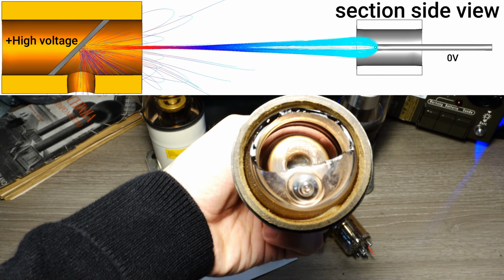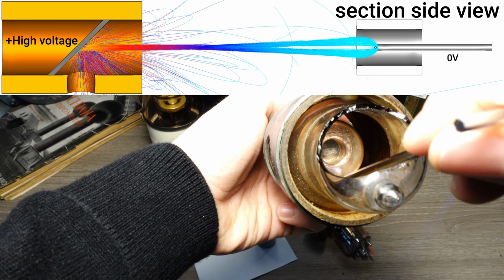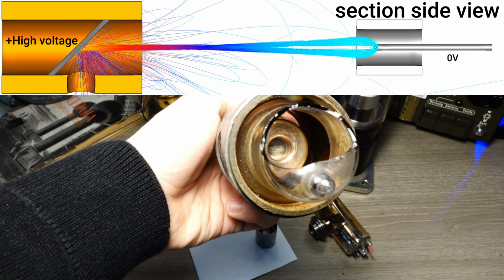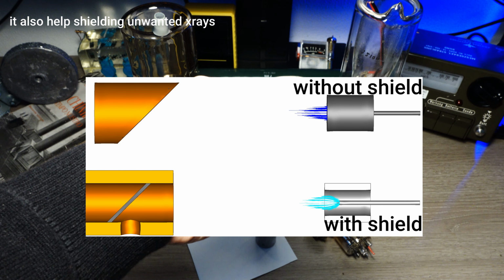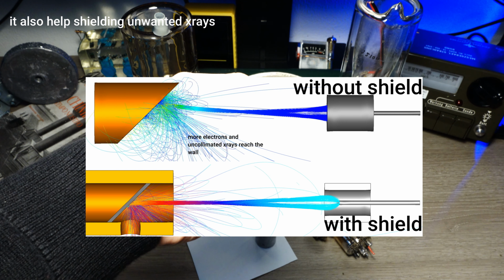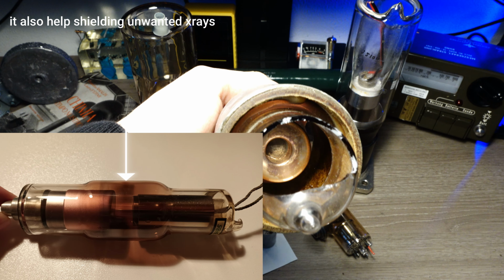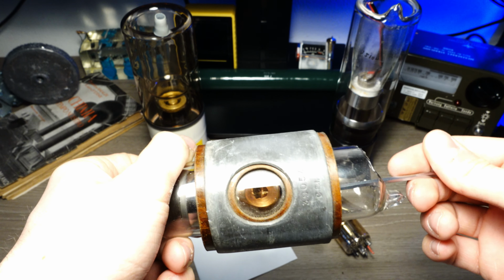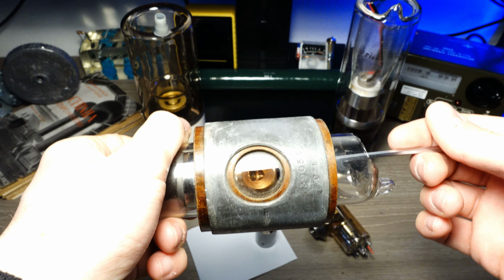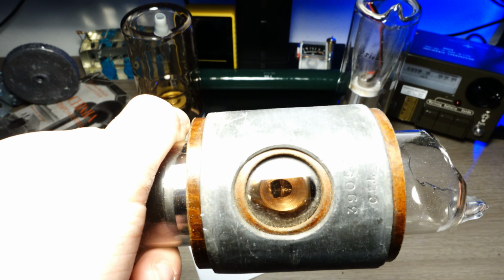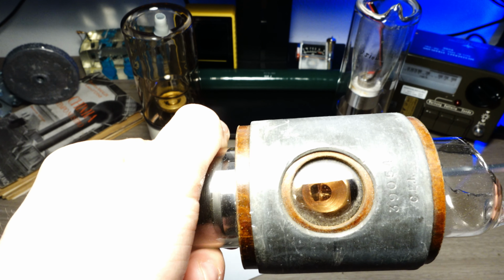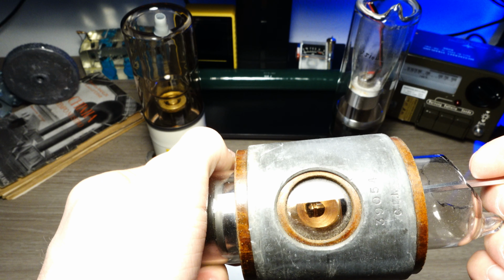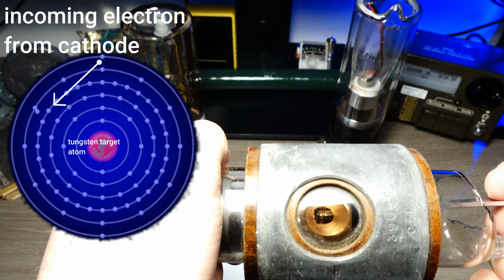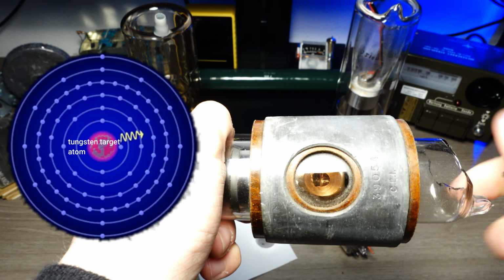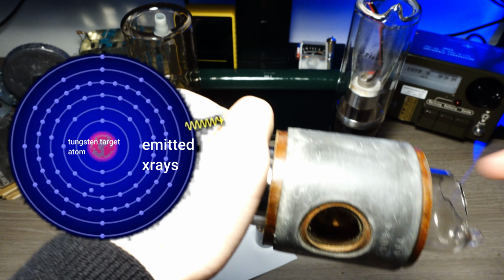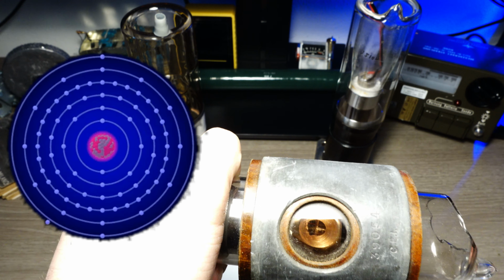this tungsten gray button. The reason for the copper outside here is to prevent secondary electrons bombardment onto the glass that will turn brownish, as you can see from this other tube. Here on the outside you can see the hole where the X-rays come from. So the electrons come from this side, enter it, go to the tungsten. They get slowed down and emit X-rays by Bremsstrahlung. The X-rays then come out of this hole and go to the target, like a patient.